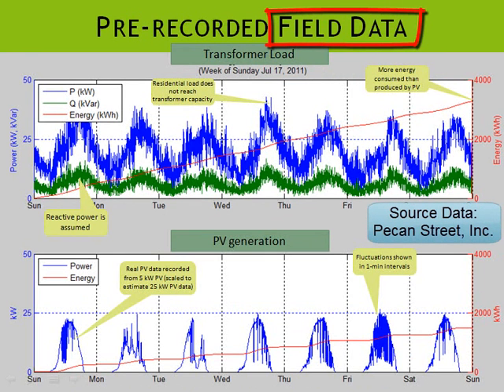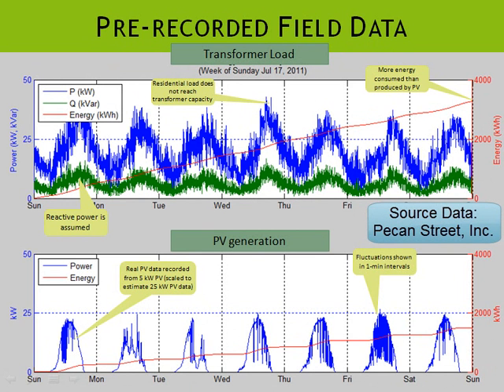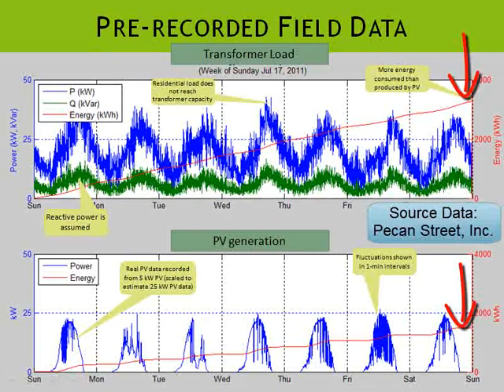Let's look at what we mean by pre-recorded field data. The following data corresponds to a week in July of 2011. The top curve set shows the residential power and energy for eight homes over one week. The blue curve shows the real power consumption, the green curve shows the reactive power consumption, and the red curve plotted against the right-side axis shows the total energy consumed by the eight homes in the course of the week. The bottom chart shows the power and energy generated by the 25 kW PV over the course of the same week. Comparing the red curves on the top and bottom, it is noticed that the eight homes consumed more energy than what the PV produced.